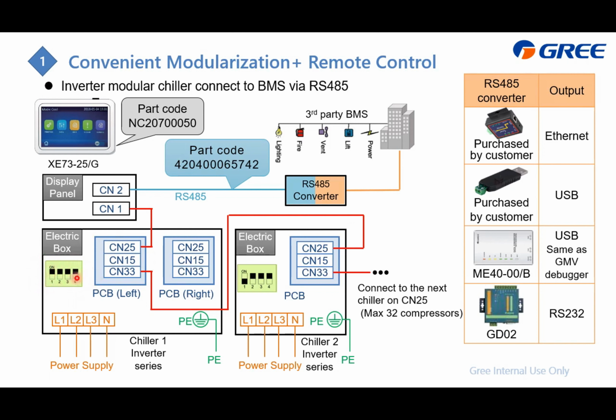If we connect the chiller with this controller, which is this one, the address should be all 0, just like this. And for this one, just change the first dip to make it bit number 2, just like this. It's okay. Also, this is the power supply, and before the commissioning you need to wire the terminals. For the modularized connection, you just need to connect from here, the CN33, to the next CN25.